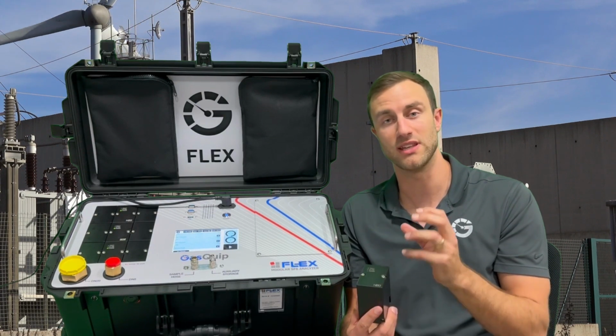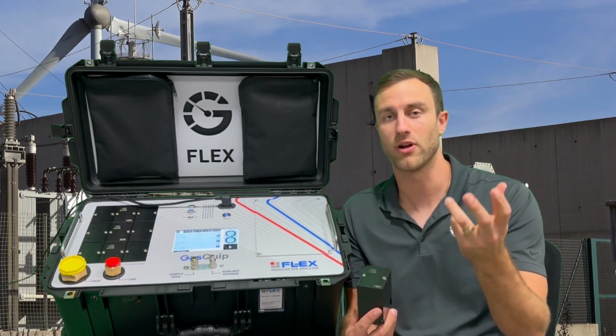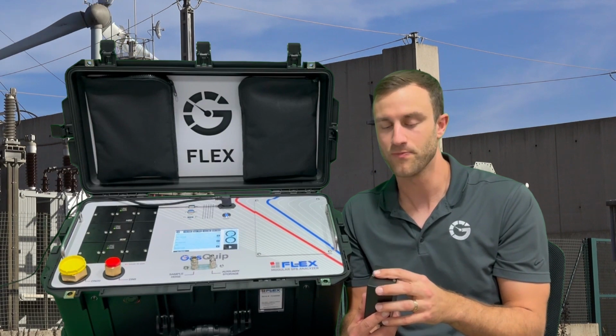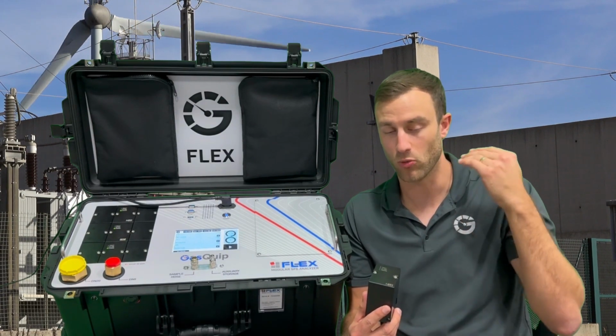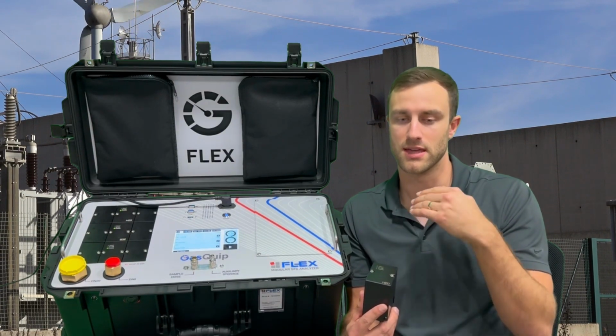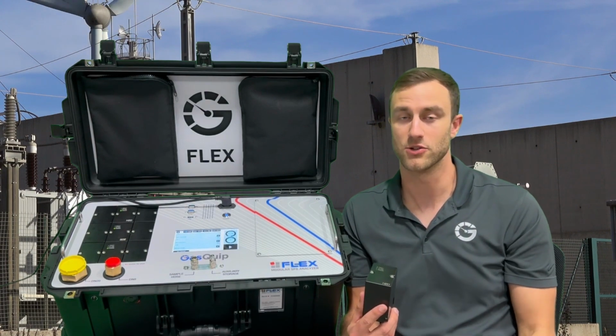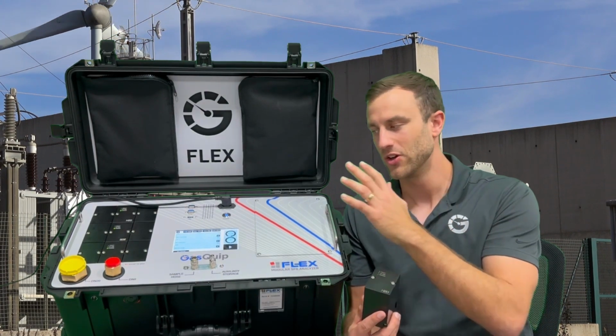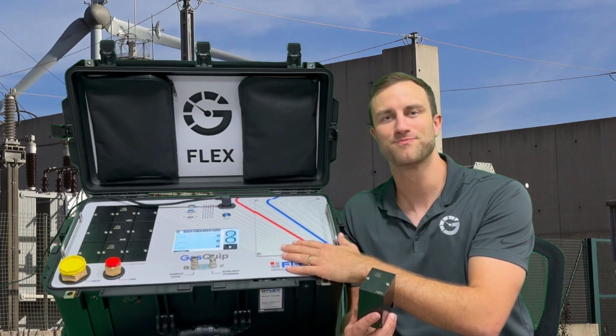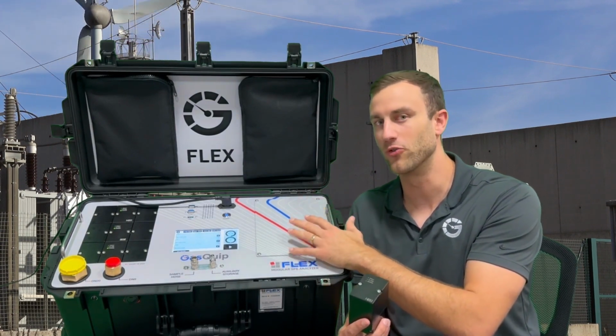But for us, we just heat that sensor up, which helps to evaporate some of that residual moisture, and that way you can trust the test right from the first test of the day, and then obviously subsequent tests after that. So those are my 5 reasons that you would go with a Flex Modular SF6 analyzer over some of the competition.